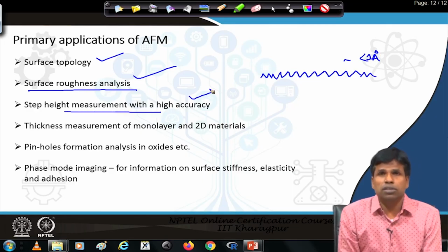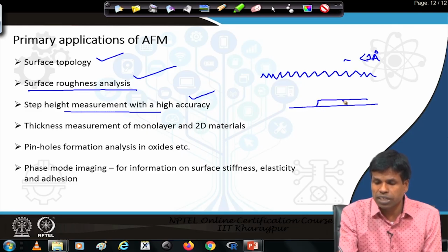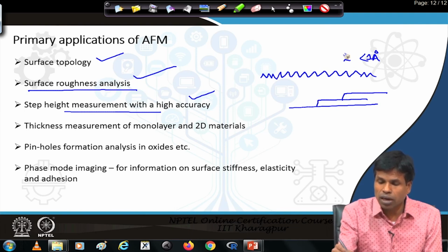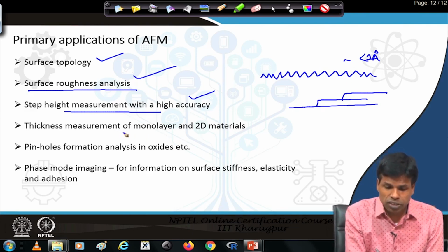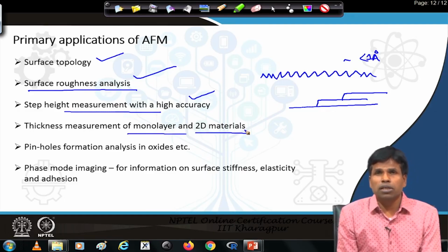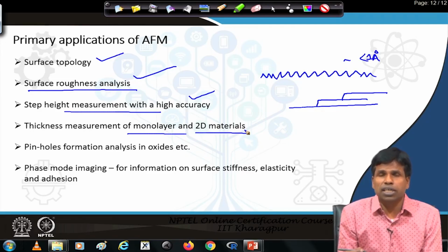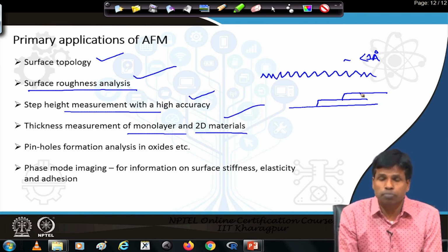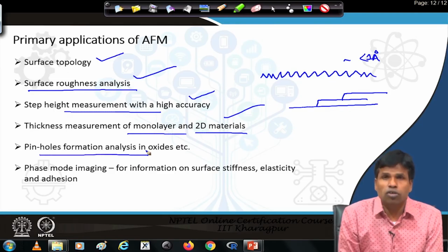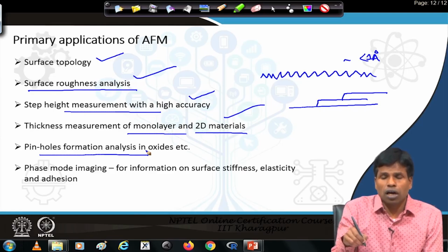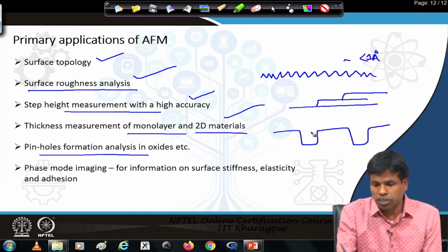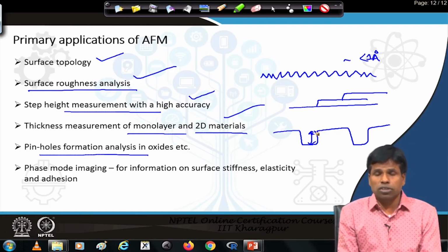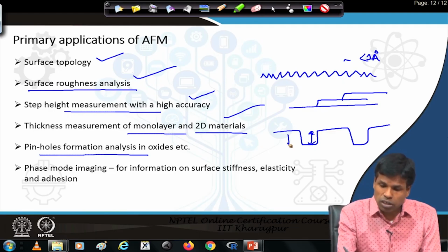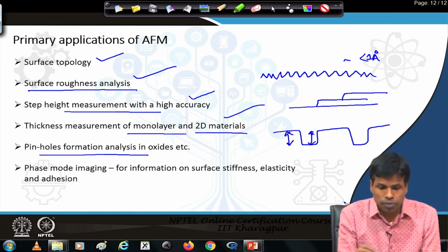Step height measurements with high accuracy. Step height means, in lithography and in device making there are different steps. We can measure the height of each step in the angstrom range. Certainly, we can measure the thickness of monolayer or 2D materials like graphene, nanosheets, all these kinds of 2D materials; thickness is most commonly measured by atomic force microscope, the same way the step height is measured. Pinhole formation analysis in oxide. If there are pinholes in a surface, we can accurately measure the height or depth of the hole, which cannot be measured by other techniques such as scanning electron microscope or helium ion microscope. Quantitatively, we cannot measure the depth or vertical height with those, but atomic force microscope and scanning tunneling microscope can be used for this purpose.